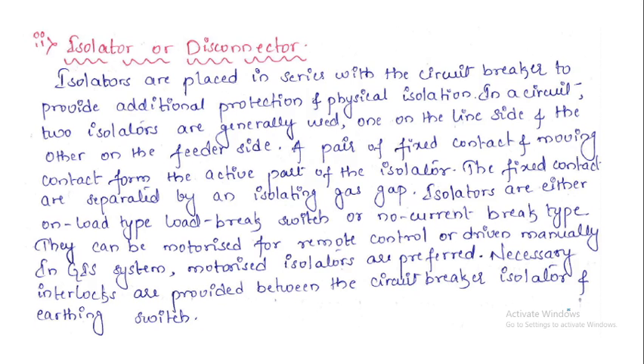Next we have the isolators, or the disconnectors. Isolators are placed in series with the circuit breaker to provide additional protection and physical isolation. In a circuit, two isolators are generally used, one on the line side and the other on the feeder side. A pair of fixed contact and moving contact forms the active part of the isolator. So it consists of one fixed contact and one moving contact, and they are separated by an isolating gas gap.